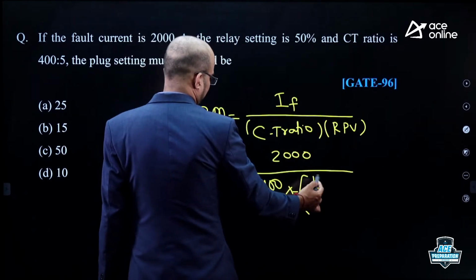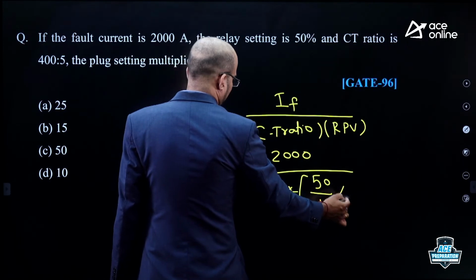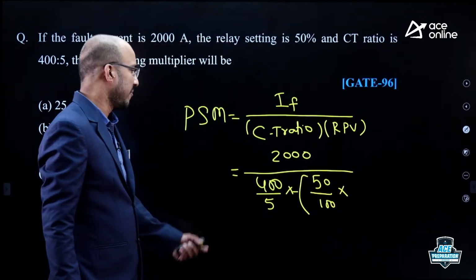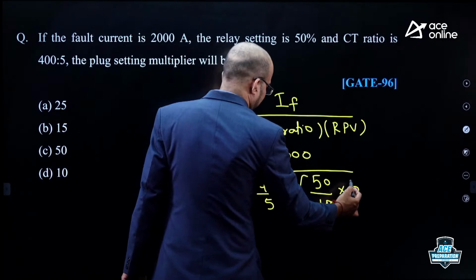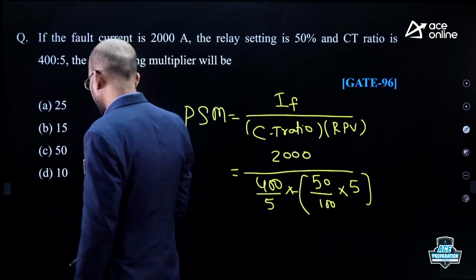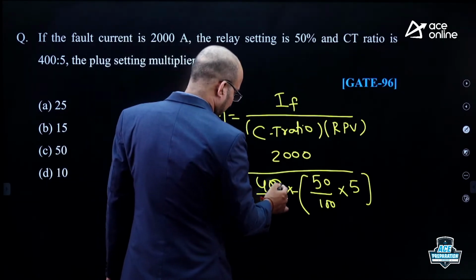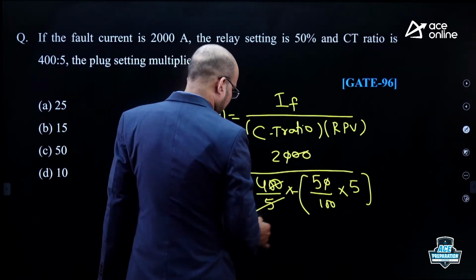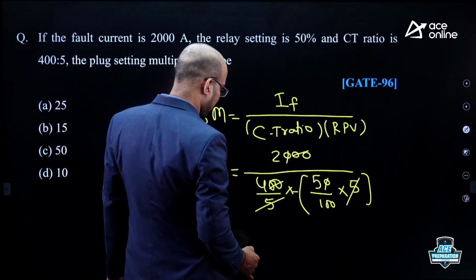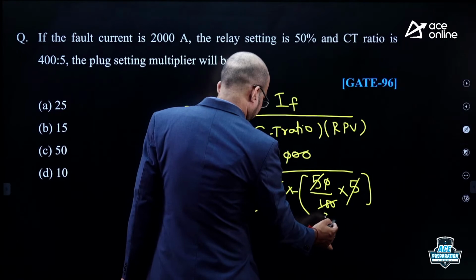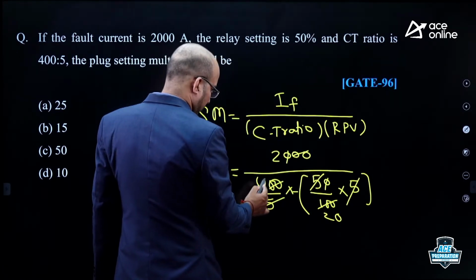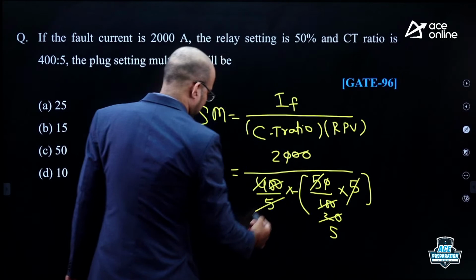Here relay setting is given as how much? 50% it is given, 50 by 100 into rating of relay coil. The rating of relay coil is not given. By default, the rating of CT secondary will be the rating of relay coil. Okay, so here if you simplify this, 200 and this will get cancelled out, this and this will get cancelled out, this 5 gets cancelled out here, and 5 ones 5, 20s 4, 5s 5, 2s 10.